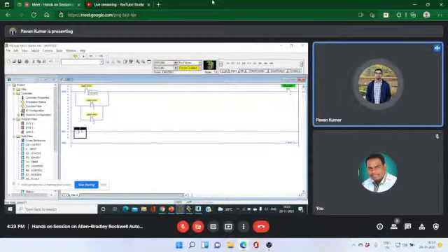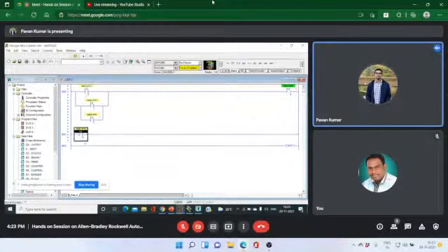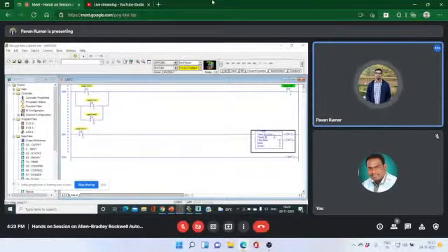the case 1 input, double click on it. When we get close to this input, it shows that green symbol. You have to place the same address as this. And I have to enable a timer. So in timer or counter bit, timer on delay, timer address as T4:0, and time base is 1 as usual.